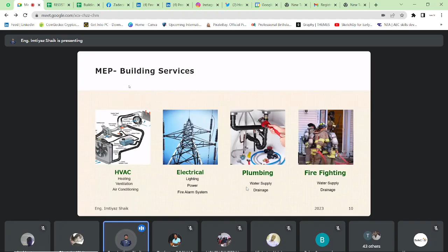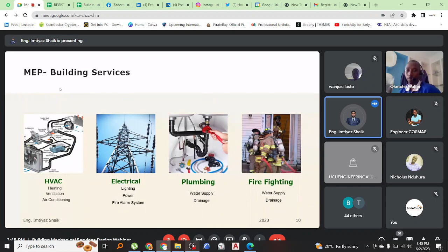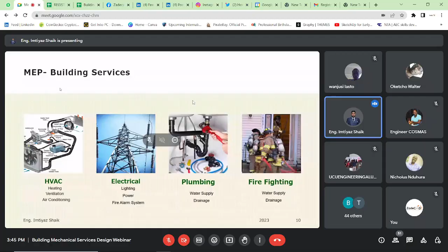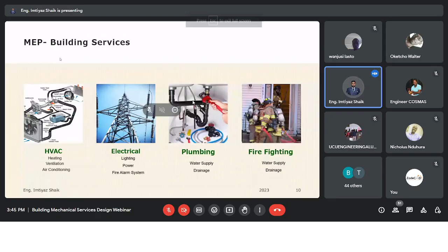Versus an apartment building where families live - in a 5-floor building, even 300 people will live there. So we need to calculate how much water is required for those buildings, and how much drainage is created. We need to design all these services properly. We cannot say you need a 100 diameter pipe for all buildings - you need proper calculations, proper water calculations, a proper underground tank, overhead tanks, and the right pumping system, all need to be calculated in plumbing design, as well as sanitary services and sanitary fittings.